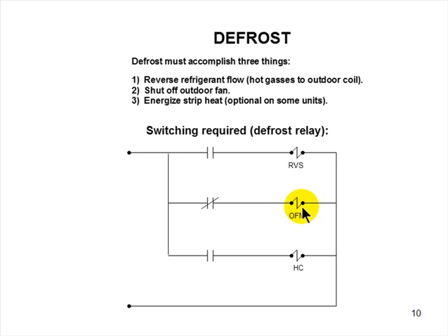And it's important to defrost quickly because we're in the cooling mode. We're blowing 50 or 60-degree air on people in the middle of winter when it's 40 degrees outside. The other thing that happens, because of that, is we're going to energize some strip heat. Most systems are built this way. There is an exception. I handled a brand of heat pumps that were made in the United States.